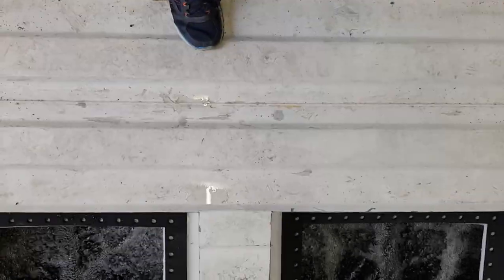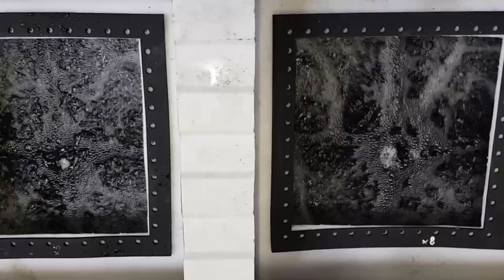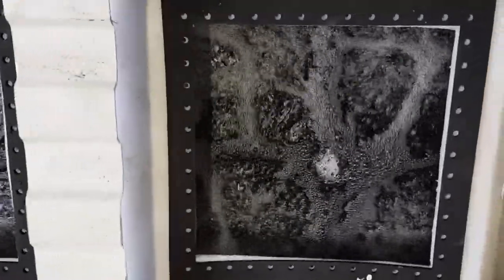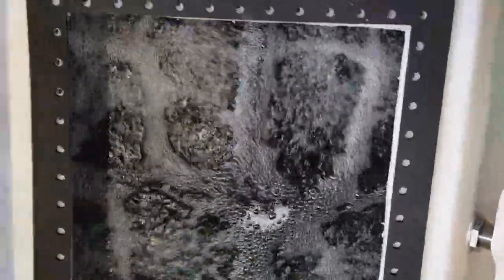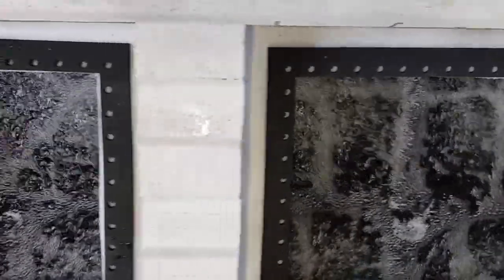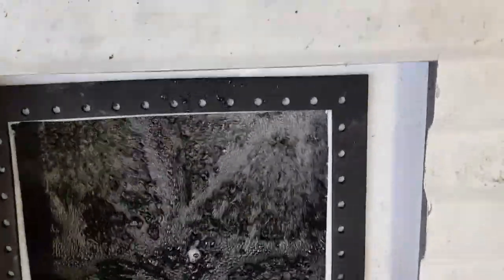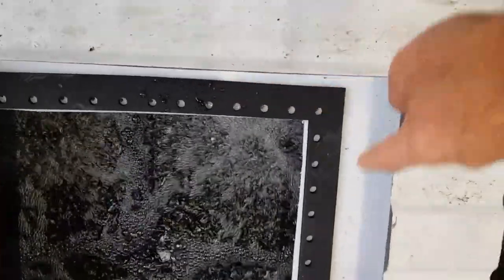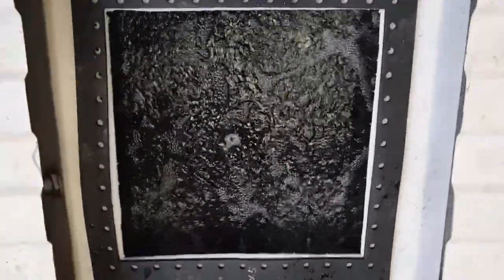We are now on the roof of the fixed bed reactor. I just want to show you during the test run of the aeration system of the membranes you see a very fine bubbling. The two openings for these two cascades are already prepared for the extensions which are sealed then and made waterproof on site.